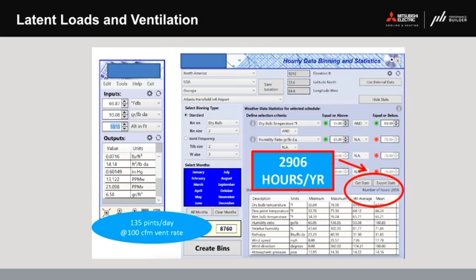So what I've done here is we're looking at psychrometric weather data. All that means is that we're looking at weather data for Atlanta, Georgia, and we're considering the number of hours out of the year when we fall into the following weather bin. When we are in a dry bulb range between 55 degrees Fahrenheit and 80 degrees Fahrenheit, which is what we also call shoulder seasons, or some people call it floating seasons. But basically, these are the hours out of the year when you're not going to get a whole lot of assistance from an AC or HVAC system, from a heat pump system, because it's just not having to work hard enough, especially not with higher performing homes. You don't have enough gains to get that system on and running continuously for long enough to remove significant amounts of moisture from the air inside your home. So we're looking at that dry bulb band.